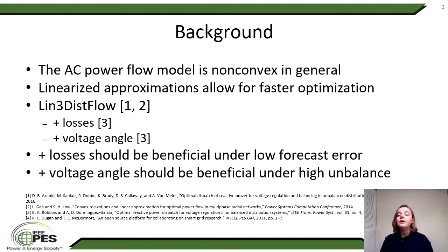So a reference power flow is where you take a forecast or a guess about what the power network is going to look like. Then you run power flow for that network and then use information from the reference network to pull into the linearized approximation, and thus you have a more accurate power flow. The improvements suggested are pulling information from the reference power flow about the nonlinear loss term such that you have a constant to represent that, and also about the voltage angle ratio such that that information can be used to better represent the losses on the lines.